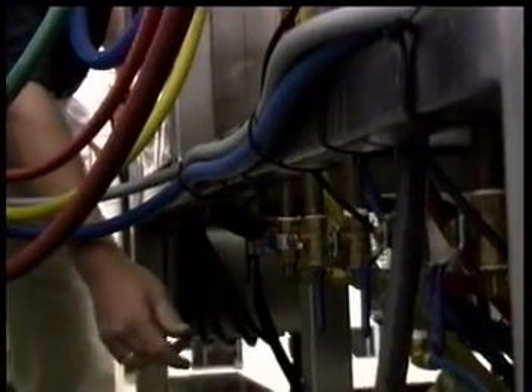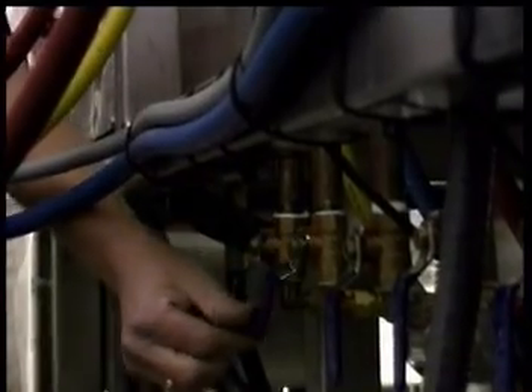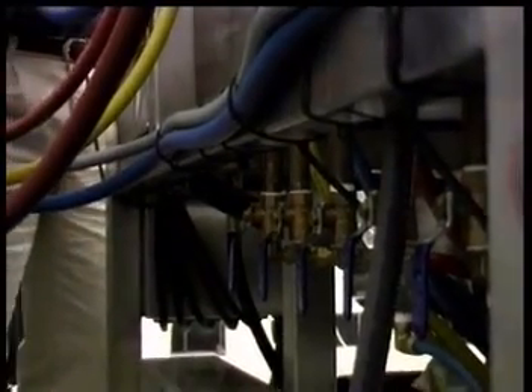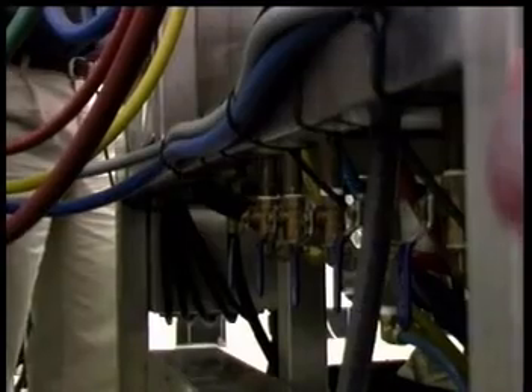The shutoff valves located on the back of the pump unit will allow you to shut off flow of product for service or repair of the chemical delivery pump. The valve must be open any time the pump is operating. Failure to do so will cause unnecessary damage to the pump.